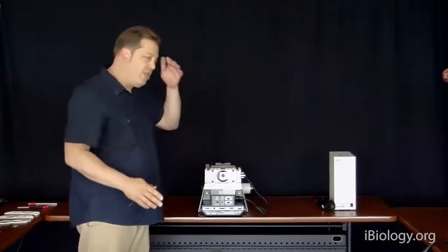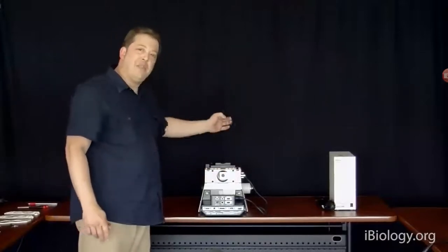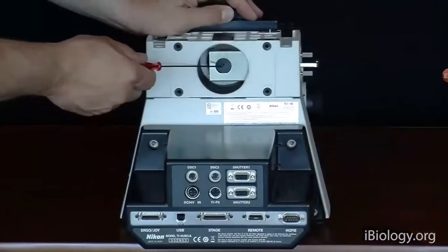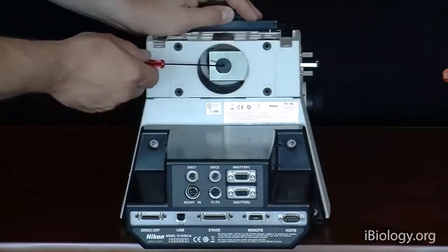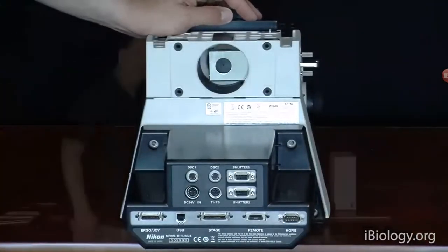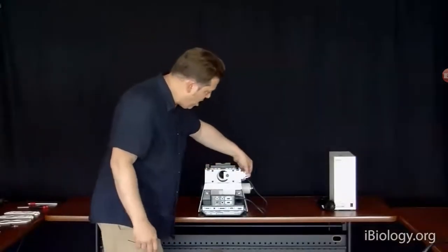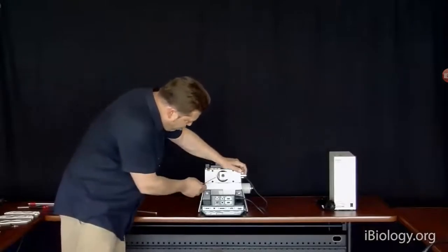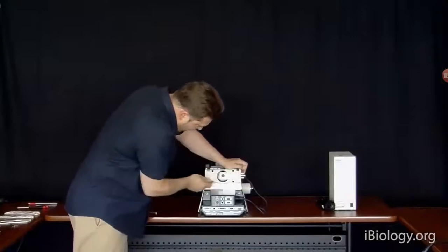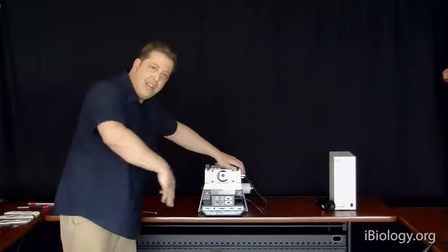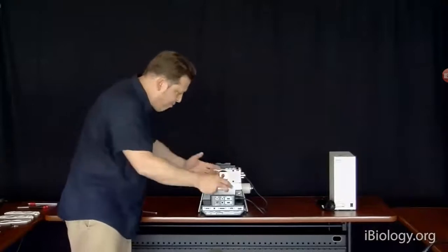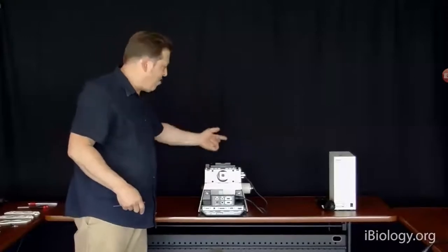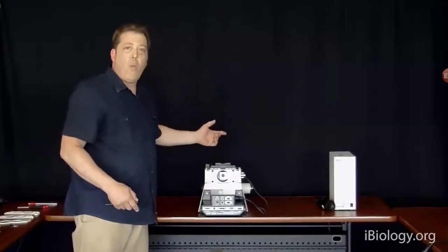However, if I wanted to focus something at the specimen of the microscope, knowing that that's a conjugate field plane, I know that if I can focus my light at this conjugate field plane, I will be focused at the conjugate field plane where your specimen is sitting. Okay. So by taking out the epi illuminator, putting this back in, I can use this as a target. And if I set up lasers or optics on a bench and I put a lens here and I focus to that plane, I can get a spot of laser light at the specimen. And why is that useful?